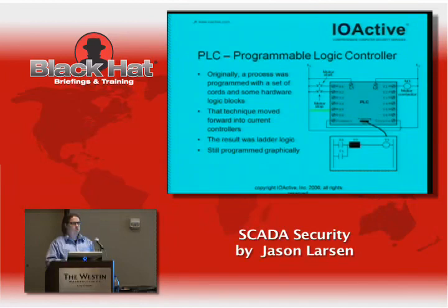As programmers, we find this really arcane and hard to deal with. But process engineers like it, it is quick to change, and they can see kind of what's going on. Ladder logic is scanned from the top to the bottom. So in this case, if Y1 is turned off as an output, you can see Y1 is actually reused as an input during the next scan cycle. So the next time it comes around, Y1 will be off and the circuit will be closed.